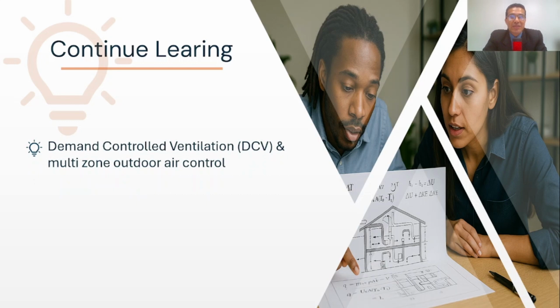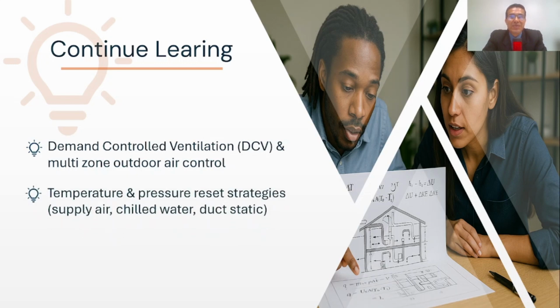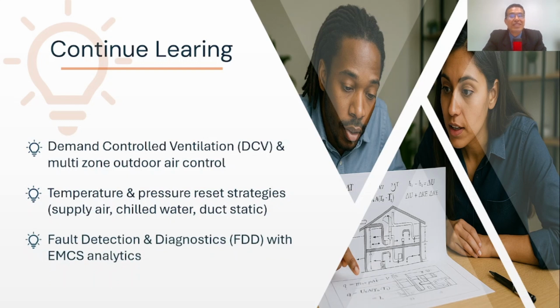You can explore demand control ventilation. It adjusts outdoor air to real occupancy using CO2 or people count signals, so a crowded meeting room receives more fresh air while a half-empty office isn't overventilated. Look into temperature and pressure reset strategies, raising supply air or chilled water temperatures and lowering duct static at part load to cut reheat and fan energy while keeping comfort steady. And check out fault detection and diagnostics, using EMCS trend data to spot stuck dampers, drifting sensors, or short-cycling equipment before complaints and wasted energy show up.